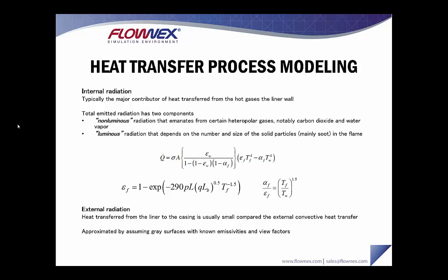Internal radiation from the hot combustion gases is typically a major contributor of heat transfer from the hot gas to the liner wall. Total emitted radiation typically has two components, both of which can be implemented in Flownex: non-luminous radiation that emanates from heteropolar gases, notably carbon dioxide and water vapor, and luminous radiation that depends on the number and size of solid particles, mainly soot, in the flame. External radiation refers to heat transfer from the liner to the casing. It is usually small compared to external convection heat transfer and is approximated by assuming grey surfaces with known emissivities and view factors.